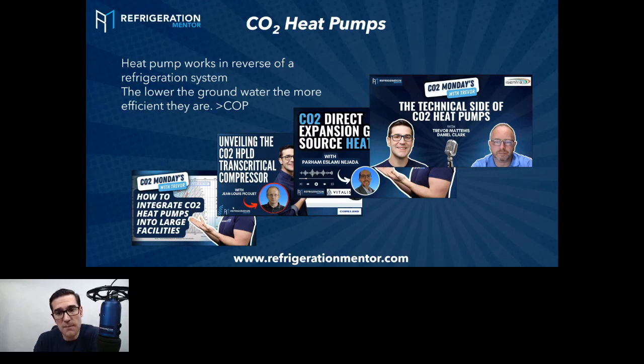I talked about the Kigali Amendment a little earlier, but didn't really mention the phase-down and phase-out. A lot of you might be using 410A right now, but because of the Kigali Amendment, what's actually happening is a reduction in the production of HFCs. Every year, or every couple of years, there's a percentage drop—going from 90% production down to 60%, then 40%. So they're cutting the amount of refrigerant being produced, which means prices are going to start to skyrocket. And as of January 1st, 2025, you can't even use 410A in chiller applications anymore.